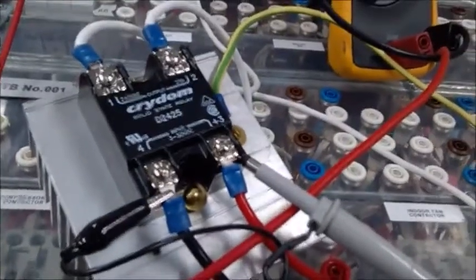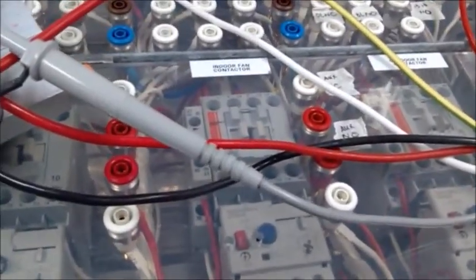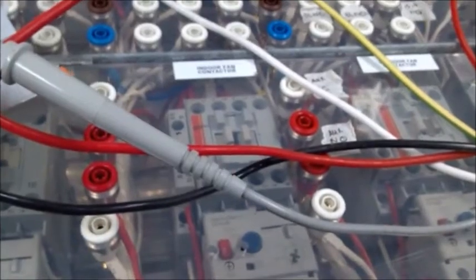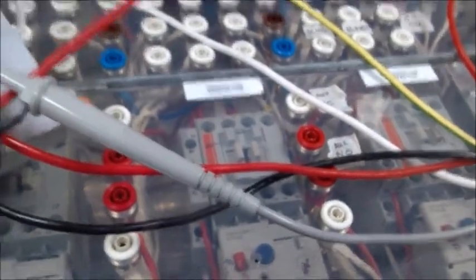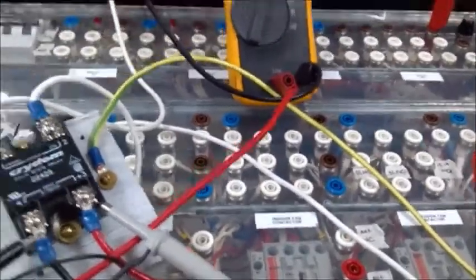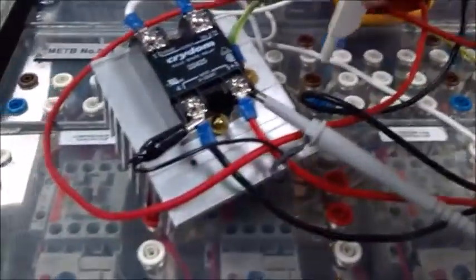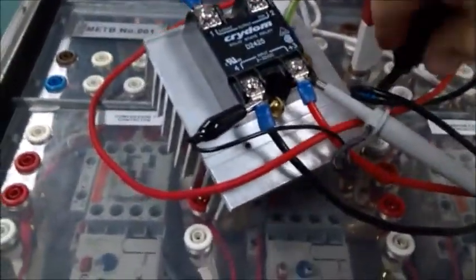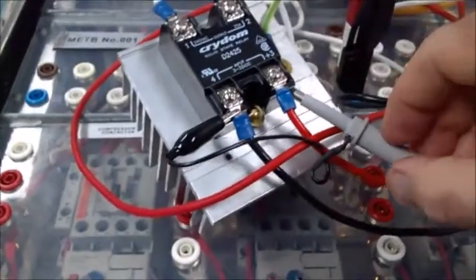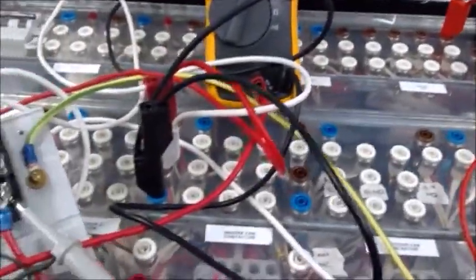You can't do this with an induction contactor. They can't be switched like that. You could not do that to the coil of an induction contactor, and I'm going to show you why. I'm going to turn this off at the moment and unplug the output feeds to it. What I'm going to do is put them into a contactor itself, and then I'm going to turn on 100 percent operation and turn on the power again.